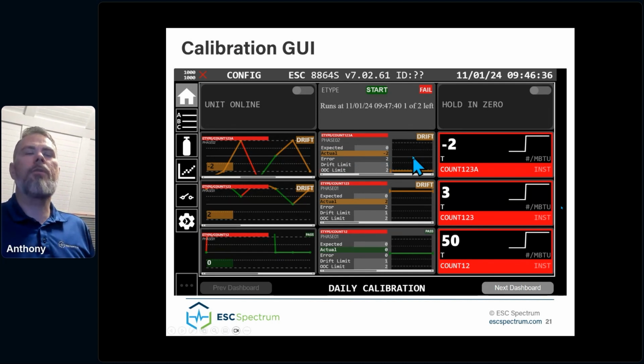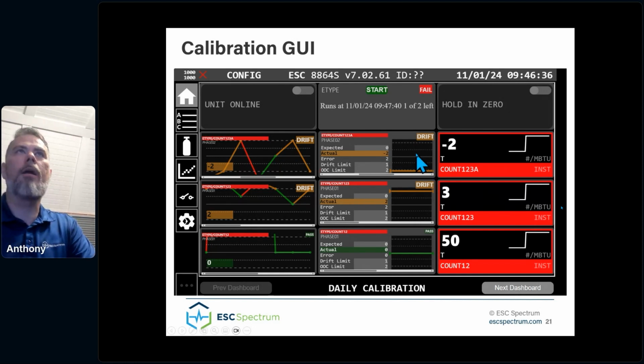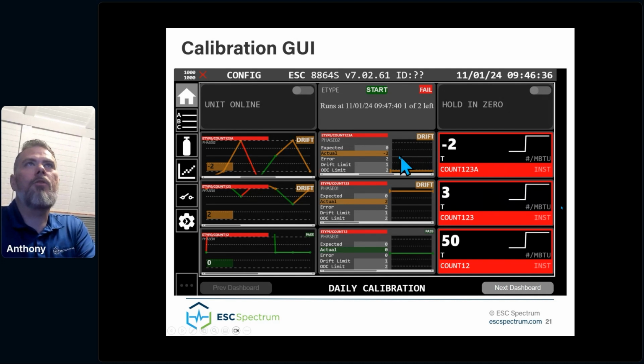Unlike the trend view, the detail view graph over here on the right will scale as large as it needs to show the actual value. So if you have some huge value that's way off scale, your drift and your OOC lines will shrink way down here and you won't really be able to see the scale on them. Both the trend and detail view show the maintenance as a dotted line and the OOC limit as a dashed line. So the trend can be thought of as an overview of multiple runs, while the detail is a detailed view of the last single run.